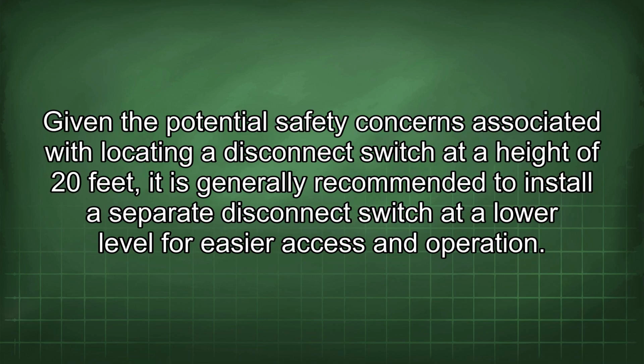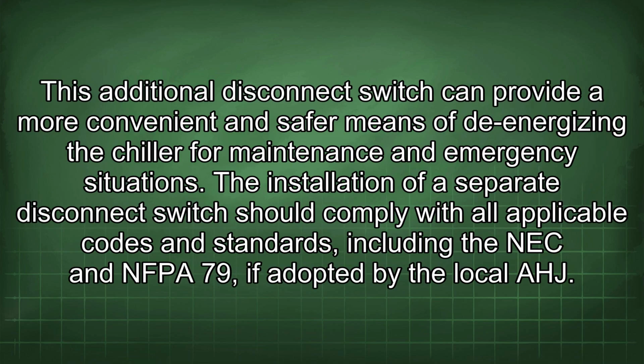Given the potential safety concerns associated with locating a disconnect switch at a height of 20 feet, it is generally recommended to install a separate disconnect switch at a lower level for easier access and operation. This additional disconnect switch can provide a more convenient and safer means of de-energizing the chiller for maintenance and emergency situations. The installation of a separate disconnect switch should comply with all applicable codes and standards, including the NEC and NFPA 79, if adopted by the local AHJ.